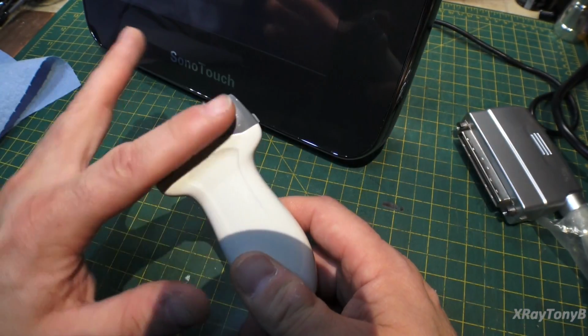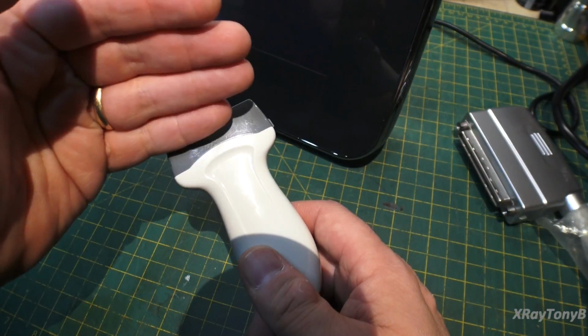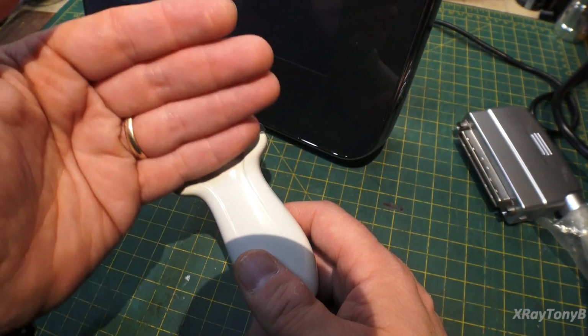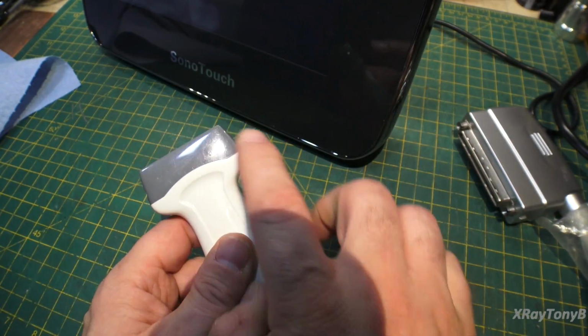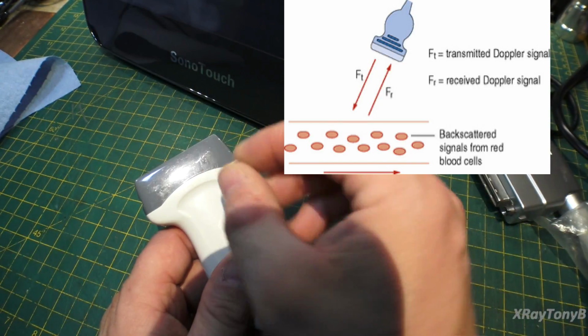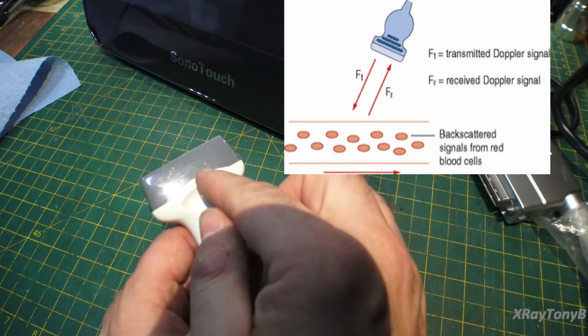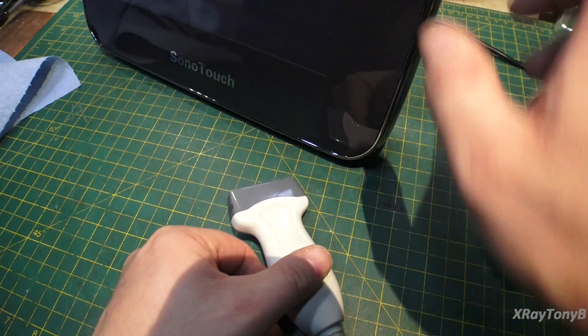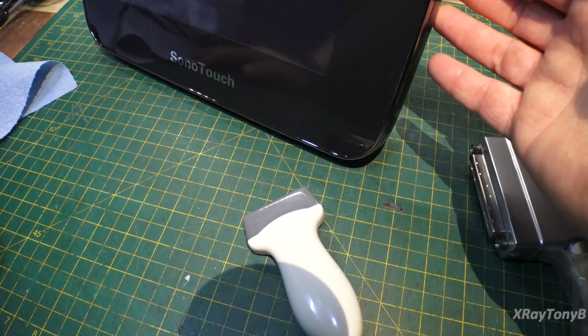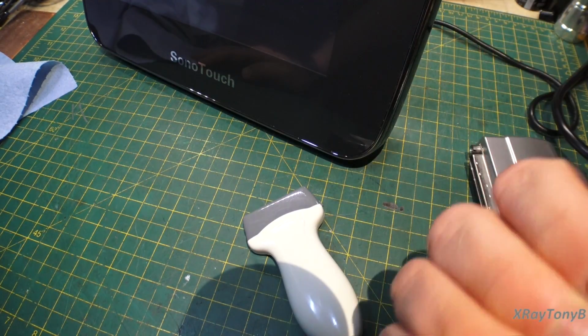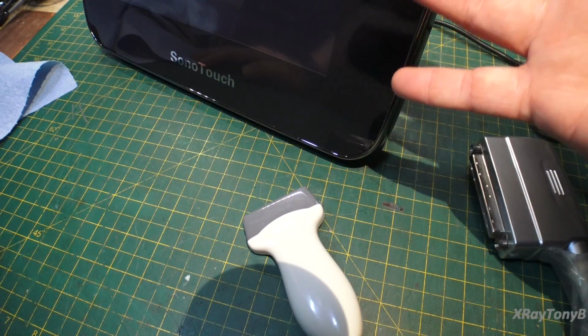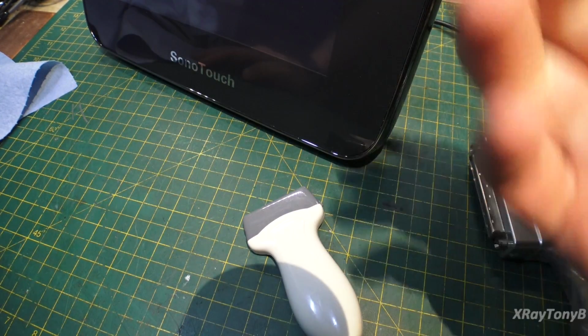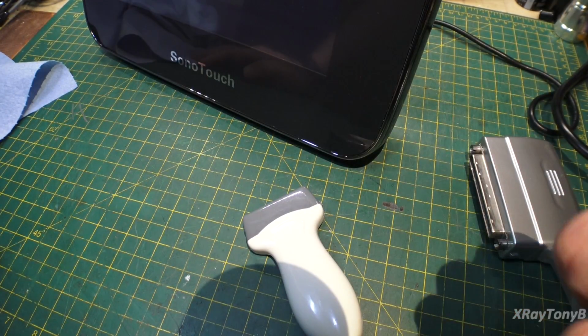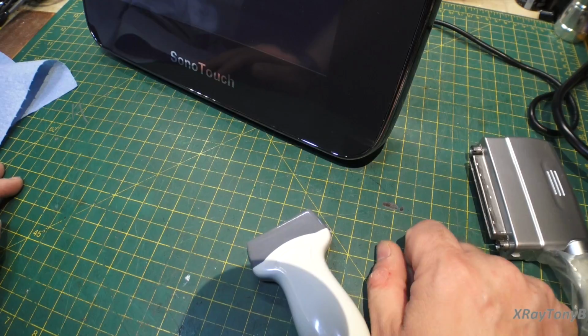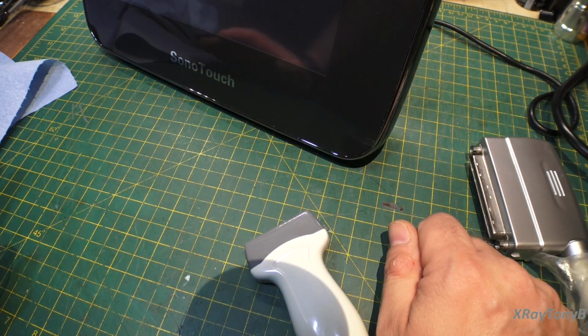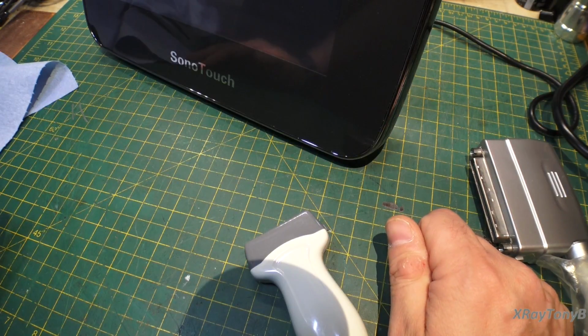In other words, they vibrate and give off a sound wave. The sound wave will then reflect off of an object and reflect back and vibrate those crystals. Since they're piezoelectric, the vibration of those will create a very small current, and that current goes through these little pins, goes into this ultrasound unit, goes through a preamp and gets amplified, and then it goes through what's called beam forming, where all those little individual channels will get put together into a two-dimensional black and white image. And through computer software, we can even add color, and we'll see what that looks like here in a little bit.